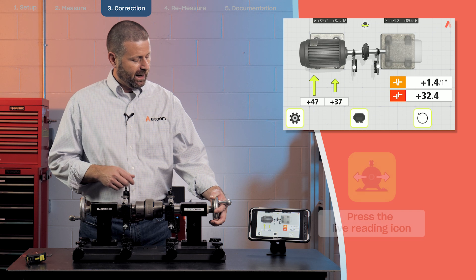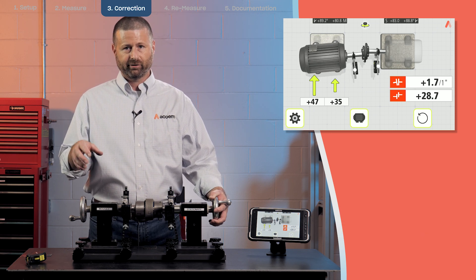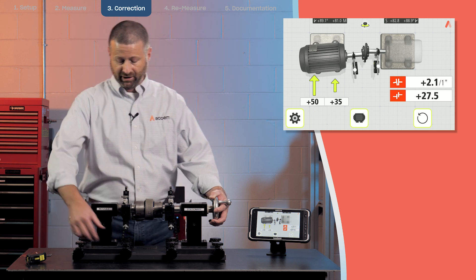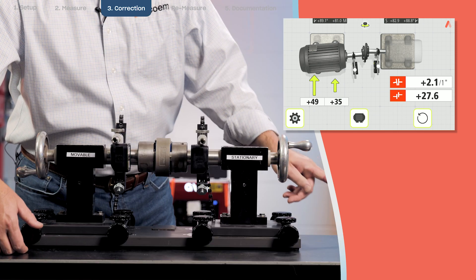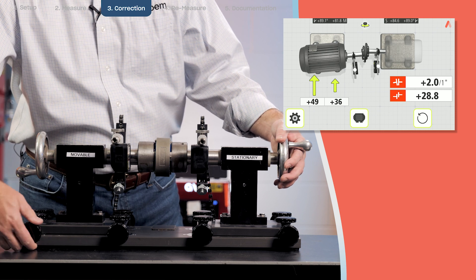So now what we have is a live picture of the horizontal. So as soon as I start moving these jack bolts, you'll see it moving on the screen. I need to go fifty thousandths in the rear and thirty five in the front. So I'm going to hit the rear one first.